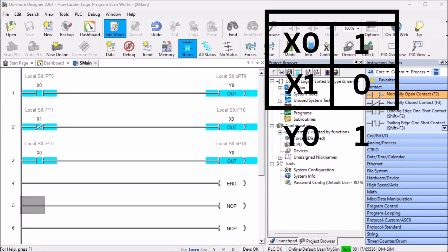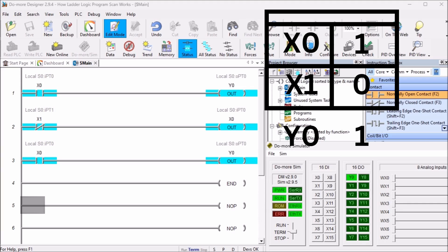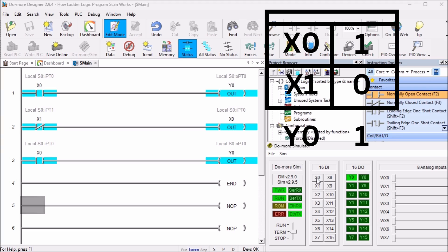The last rung of ladder logic code will always overwrite anything previous in the memory table. An excellent method of troubleshooting logical errors in the PLC would be to move the rung with the output to the end of the scan. This will allow the rung to be the last to update the memory table before writing to the physical outputs.